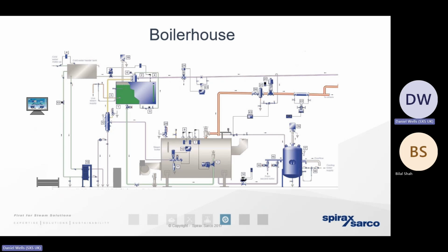So there are a number of different controls and ancillaries that will furnish the boiler. There are many, many different types of boiler controls: level controls, water chemistry controls, safety controls. And the function of these controls is really to ensure that steam's being produced very rapidly and responsively, to ensure that we're producing the steam with a minimum of energy consumption. We want to keep the gas to an absolute minimum. We want to keep the quality of the steam as dry as it possibly can, so it exists at a condition that's as close to that red, dry, saturated steam line as we can. Most importantly of all, we need to keep the boiler operating safely.